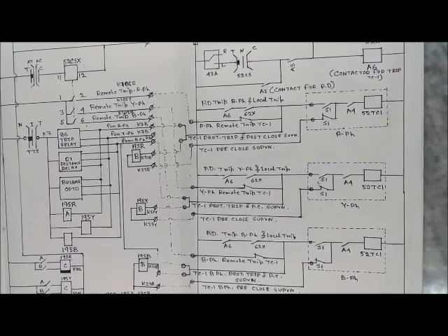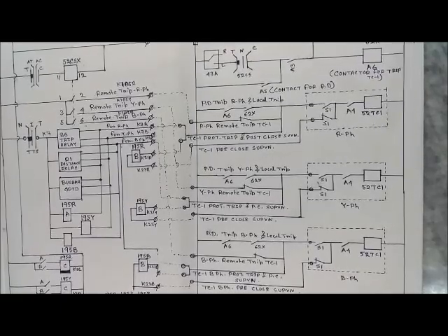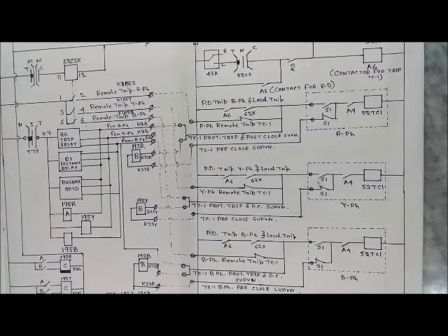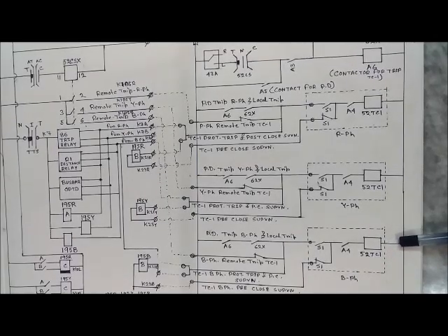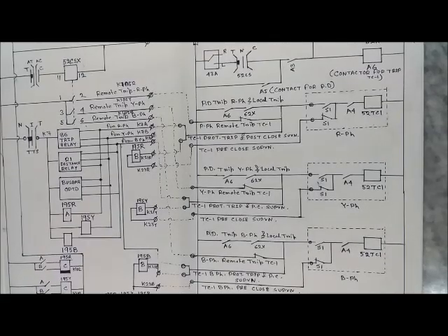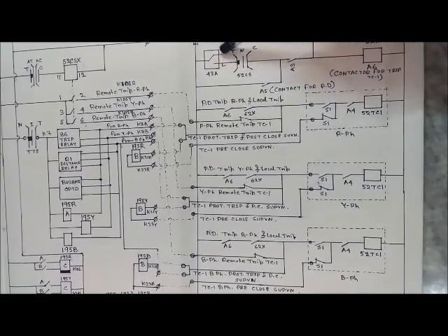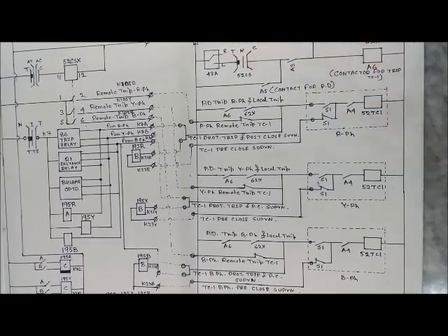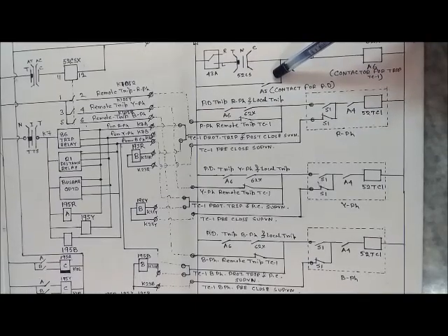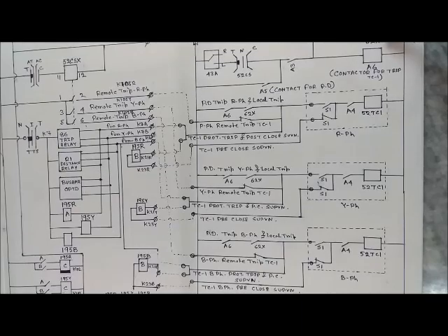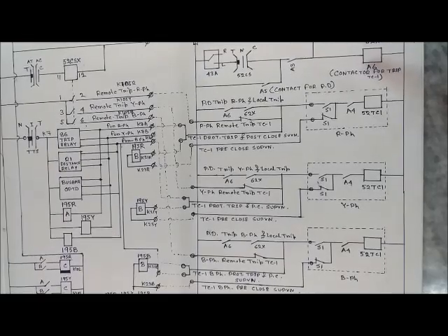For the trip circuit, the diagram shown is for TC1 of the circuit breaker. The right-hand side portion shows the circuit breaker portion and the left-hand side shows the control and relay portion. 52TC1 is trip coil one of the circuit breaker for R phase, Y phase, and B phase. Similarly, there exists trip coil two. TNC is the local control switch, 43A is the local/remote selector switch. A5 is the contact for pole discrepancy trip, and A6 with 62X is the contactor for trip one.